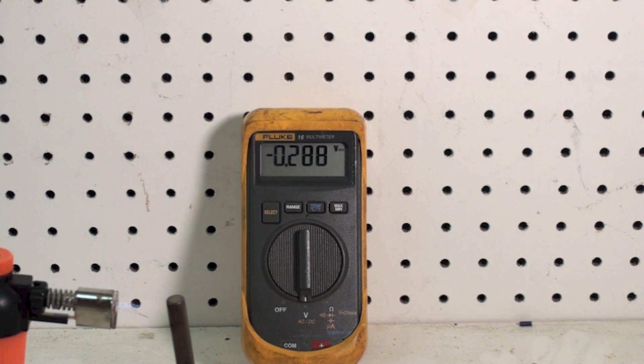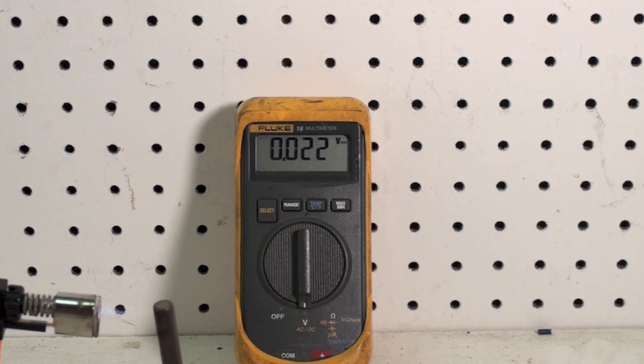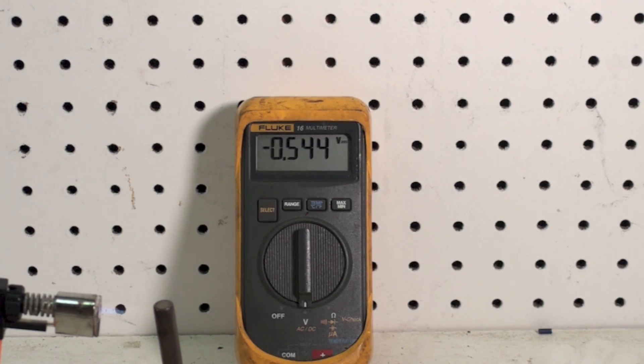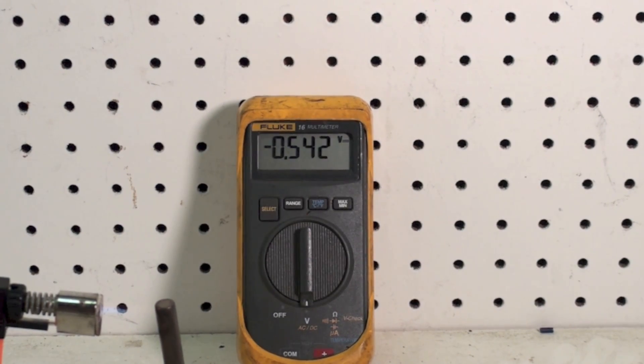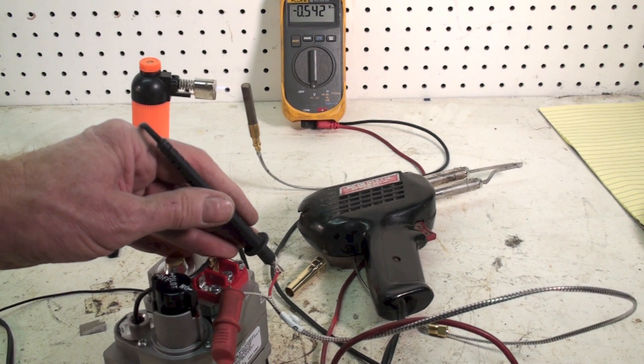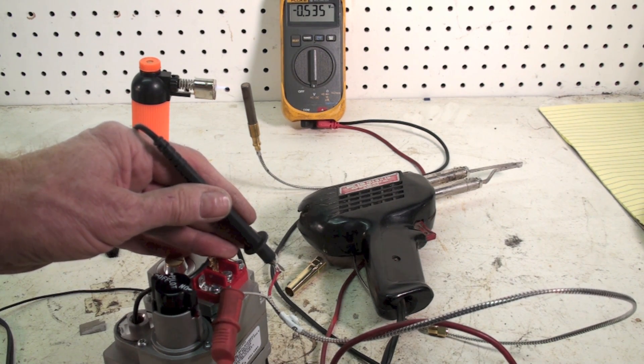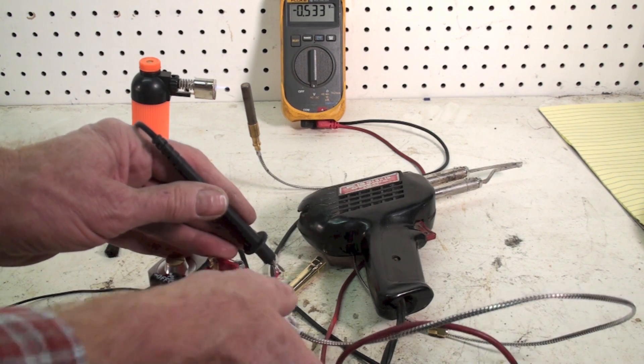That five to six hundred went down to 287. I'm going to pull this off and I'm putting the probe back on. You see I've got 544, and let's get this to where you can see a little better. We got 544 millivolts with the wire off the gas valve.